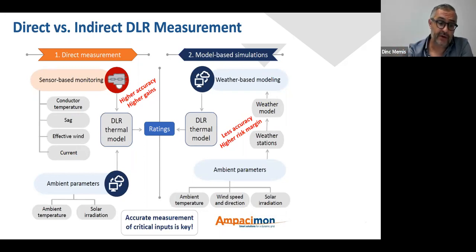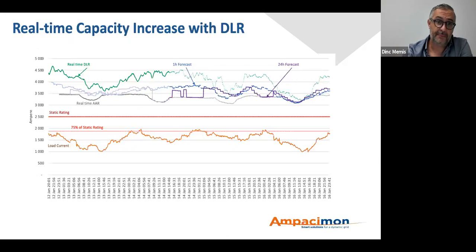On the next slide, I want to show you a real-time example, where you can see the differences between these two methodologies. On one of the lines, our sensors are installed. As you can see, the load current of the line, at the bottom, is operating at 75% of the static rating with the safety net, and you see where the static rating stands. This is a measurement over a 4-day period, and you can see the capacity gain coming with the real-time AAR.